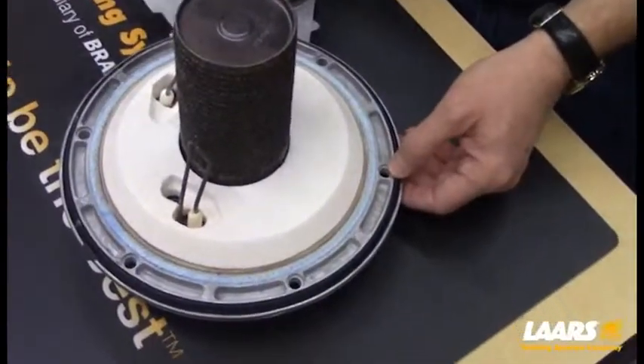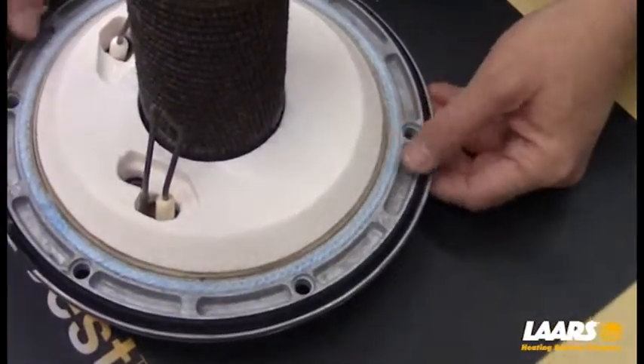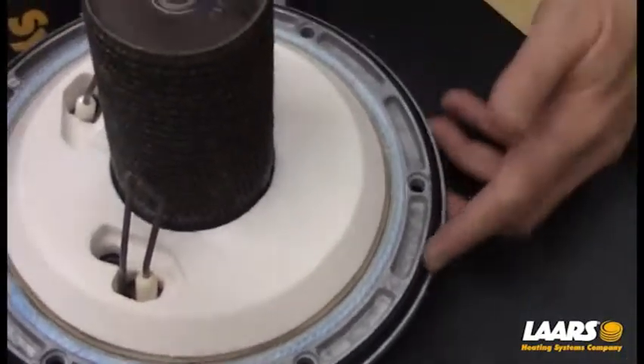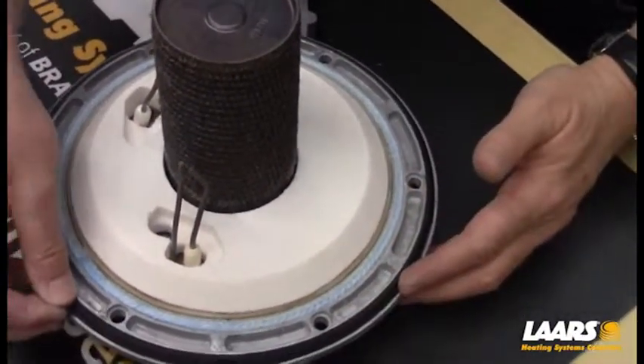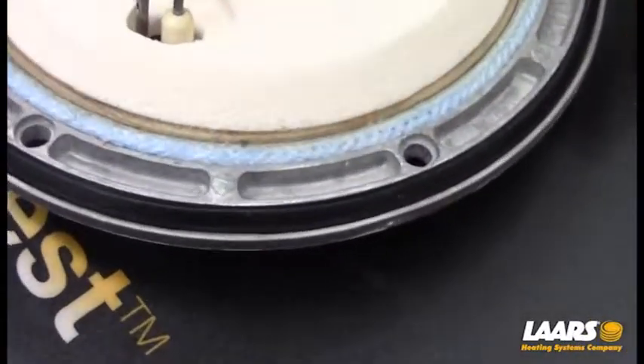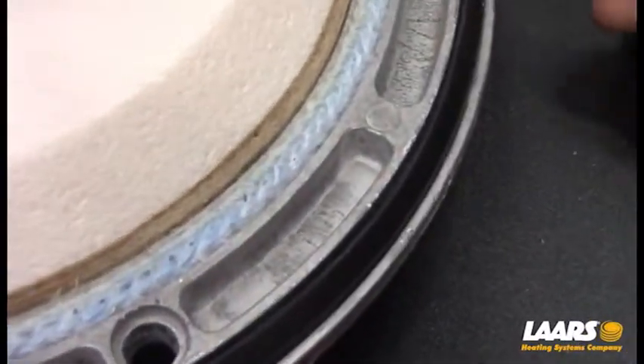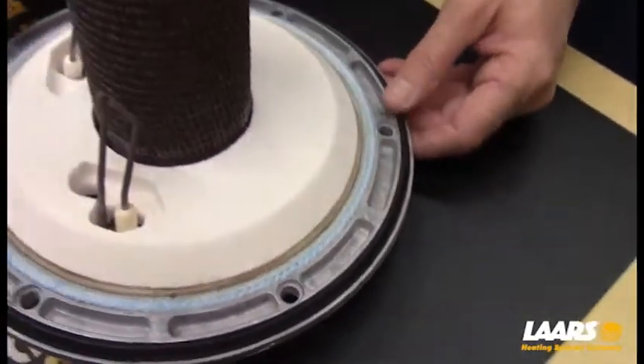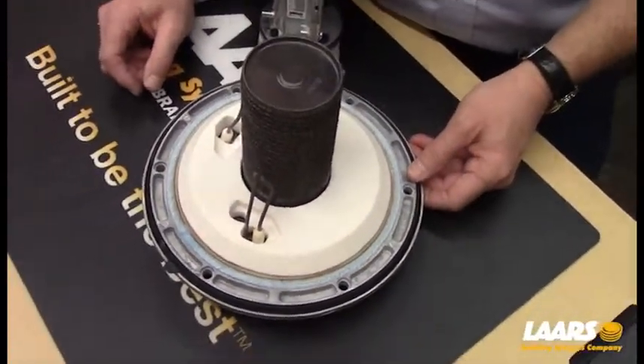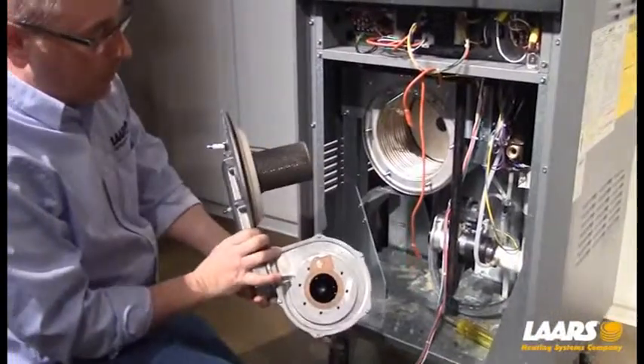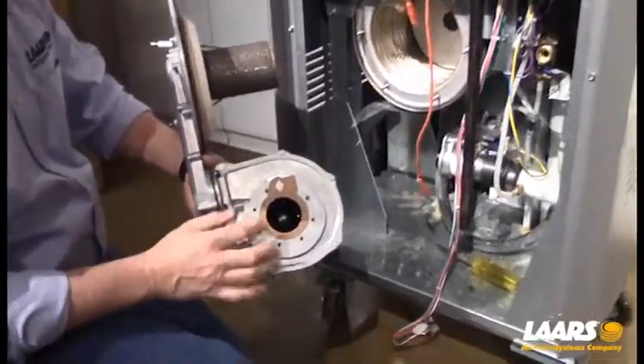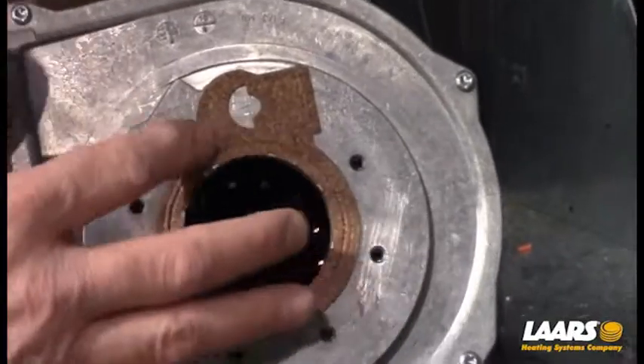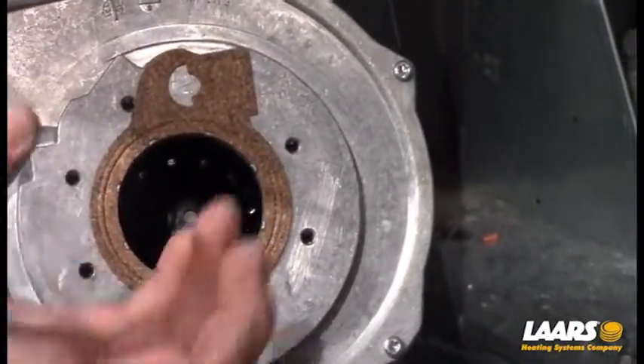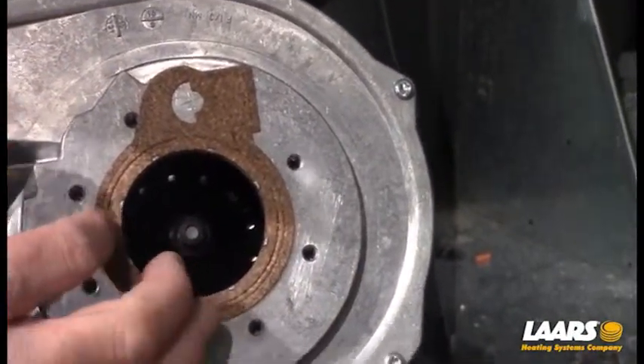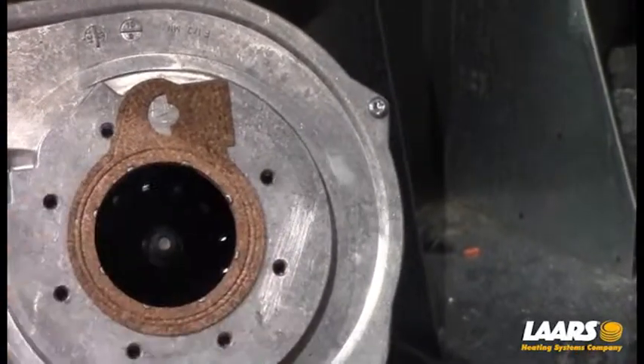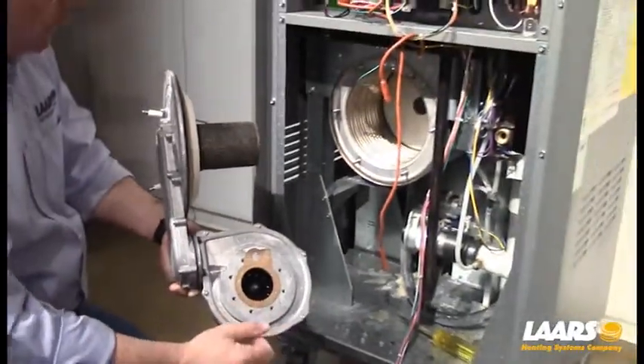You'll see 2 sets of gaskets here on the burner plate. These gaskets are reusable, but inspect them. Make sure they're not damaged. If needed, you could replace these, but you can reuse these if there aren't any issues with them. So just inspect those gaskets before you put the burner head back into position. Okay, so now we're going to put the burner back into position. Prior to doing that, I also want you to inspect this gasket. It's a cork type gasket, the venturi mounting to the blower. It is reusable. Just make sure you don't have any tears or anything on it, and be gentle with it. If needed, you can order it.